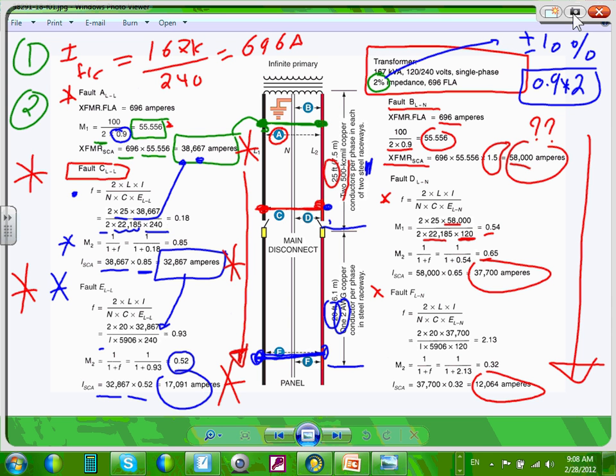I want the equipment to be far away from the transformer, so the short circuit will be low, so my equipment will be cheap. Great idea, Chad. Oops, wait a minute. If you move your equipment away from the transformer, what happens to the voltage drop? Goes up. So you're going to find that happy medium between the equipment being far away and the voltage drop issue, as well as close enough and the short circuit issue. I always tell when I do the training, the only advantage of having equipment far away from the source is the short circuit will be lower. Lower means better. Short circuit lower means less damage, less arc flash, arc fault, arc blast. So it's safer equipment.